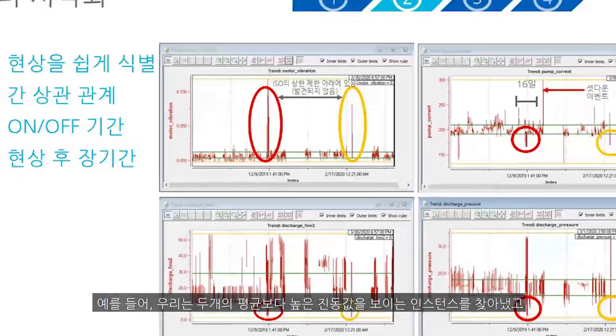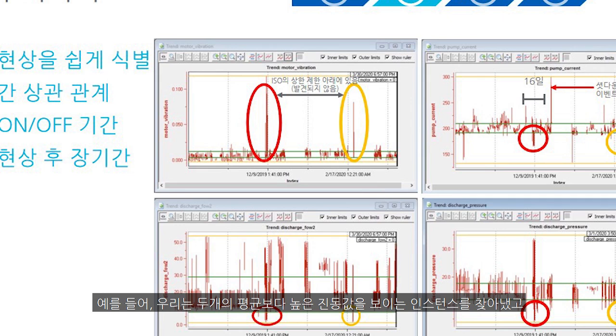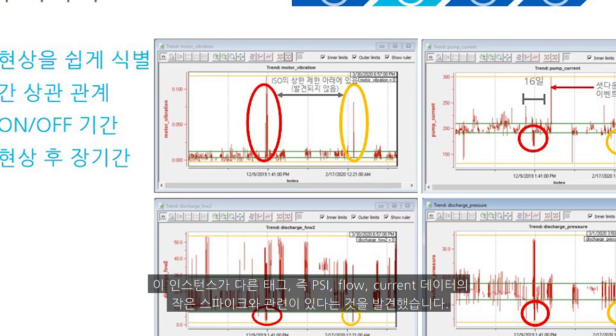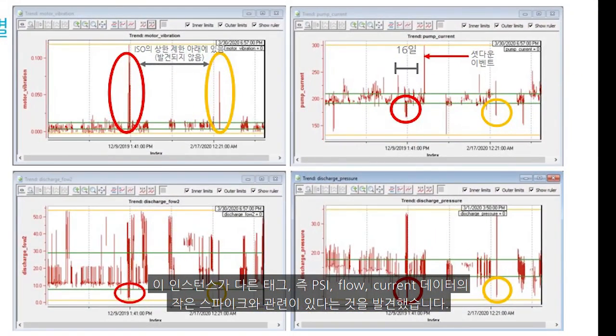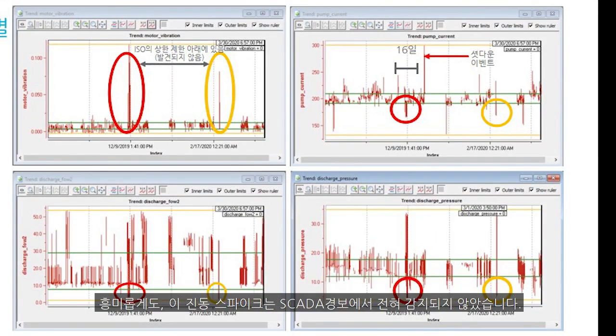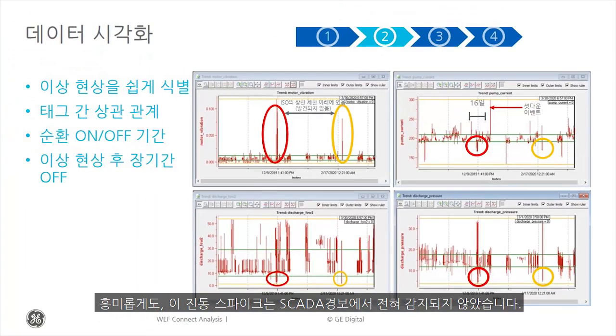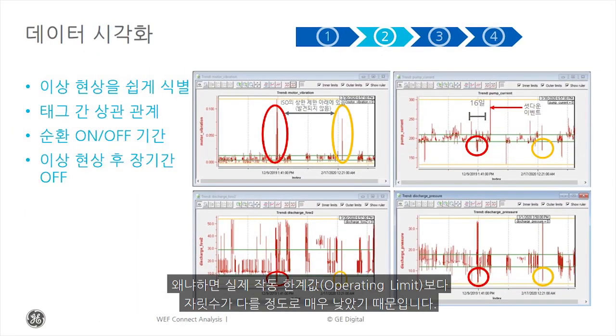For example, we found 2 instances of higher than average vibration that appeared to correlate with smaller spikes of data with other tags, such as PSI, flow, or current.